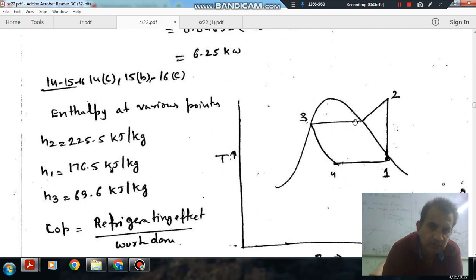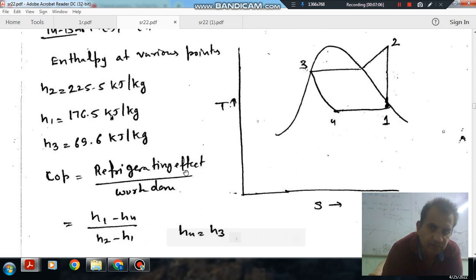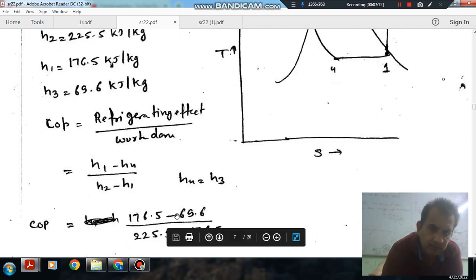The enthalpy at point 2 is H2 equals 225.5 kJ/kg, H1 is 176.5 kJ/kg, and H3 is 69.6 kJ/kg. The COP is H1 minus H4 divided by H2 minus H1, and H4 is equal to H3.